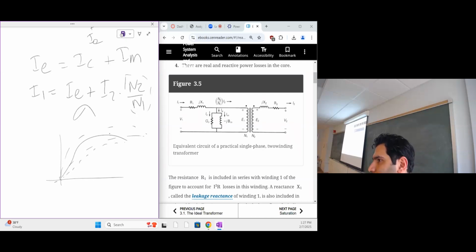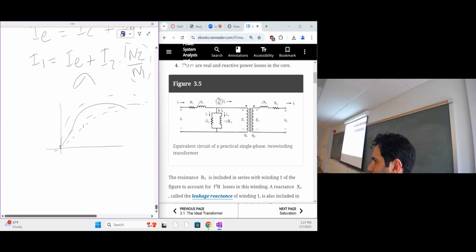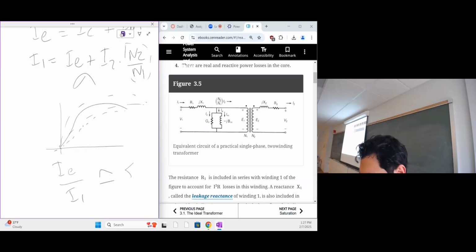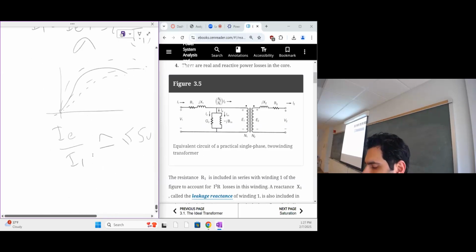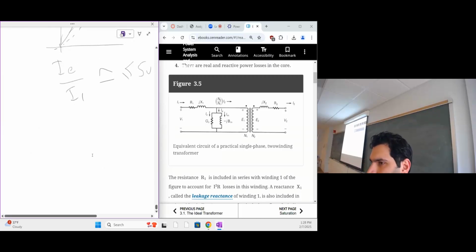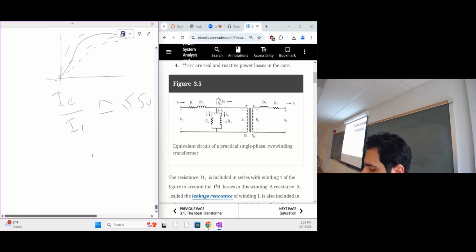Magnetization relates to the initiation of flux in the magnetic material, and typically that tends to be a transient effect. If we add up those two losses, they make up the excitation current in the transformer, and this will be a small percentage of the total current I1. So if I'd like to calculate the efficiency of this transformer, I would calculate IE over I1 to see how much that is—it should be less than 5%. If more than that is consumed by the magnetization process or core losses, that means the transformer isn't functioning properly, or there are issues with the magnetic material itself.